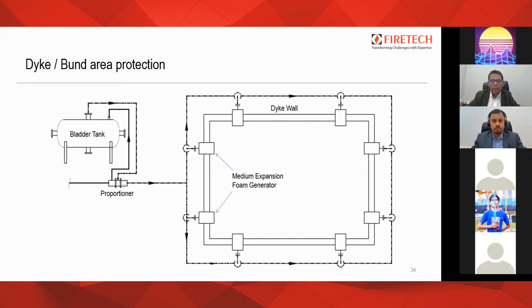In due course, due to some fracture of the piping or of the sealing elements like gaskets, there are chances of flammable fuel spilling into the dike. Once a dike spill catches fire, the whole of the tanks as well as the dike are engulfed in fire. In this case, medium expansion foam generators are mounted around the dike.